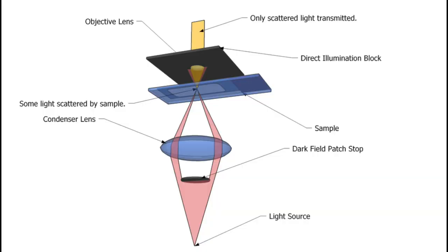So why does this work? Well, it's a bit of an optical trick that uses the fact that a decent microscope has a little lens underneath the sample to focus the light onto it. By blocking the middle part of the light before it gets to that condenser lens, when the light is focused onto the sample, there's still more than enough to illuminate it, but the direct light is gone, giving it the black background effect that we want.